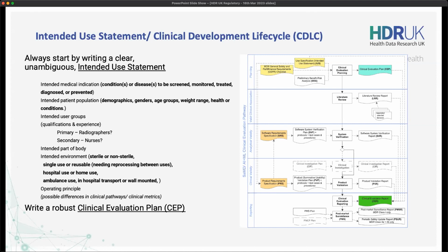Very quickly, you create a plan that says you do the first step we call valid clinical association or scientific validity of your solution. We start with literature review. What does the scientific literature and what does the regulatory literature? So the regulatory databases, general, a bit of structured Googling, but very systematic scientific literature review. And we do ours based on PRISMA guidelines for how to perform the review in a systematic, structured way. What does the existing peer-reviewed robust literature say about why is what you're doing valid?